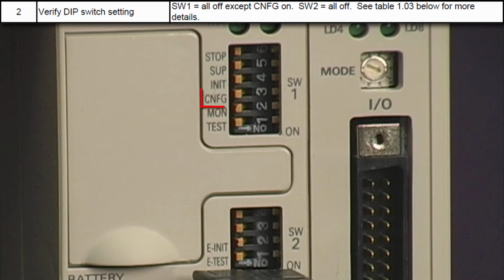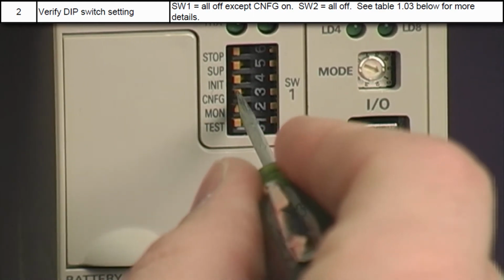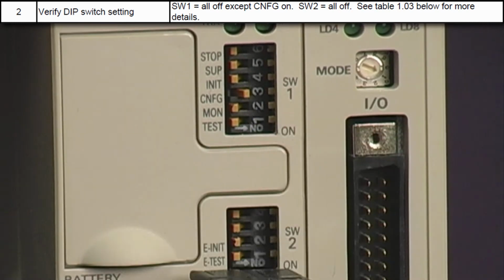Next, check the DIP switches. Only the config switch is normally set on. All the others are normally set to off. Config on at power-up allows the controller to discover Mechatrolink devices and local I.O. cards, but it does not affect the operation of the controller.